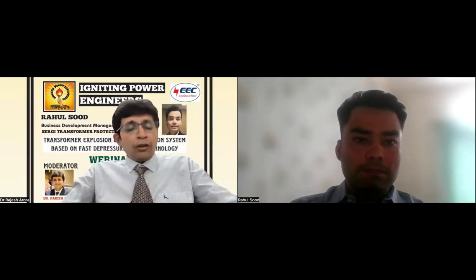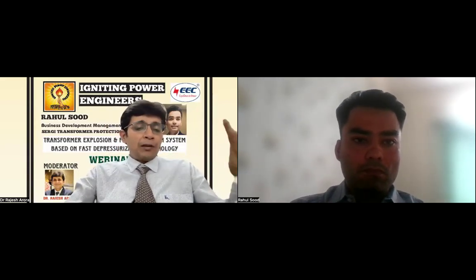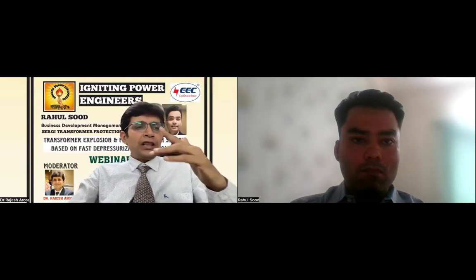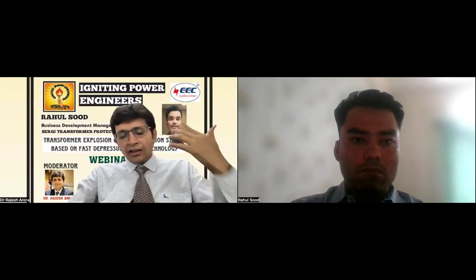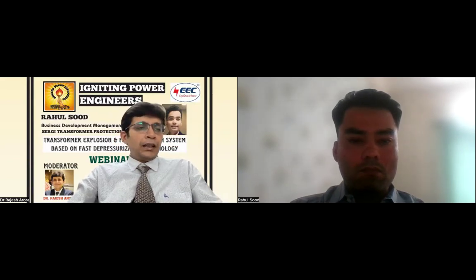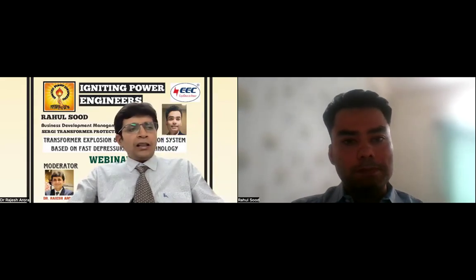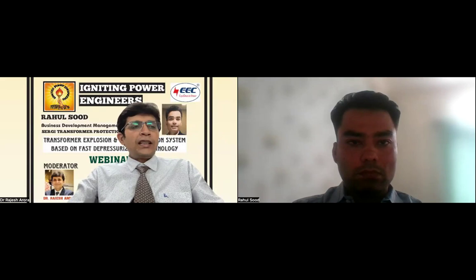Now, I would like to give some data available in the public domain. In the last 4 years, 2021 to 2024, as per the data available on the CEA site, there were 33 major transformer and reactor failures. 220 kV failures were 10, 400 kV were 19, and 765 kV reactors and transformers included 4.